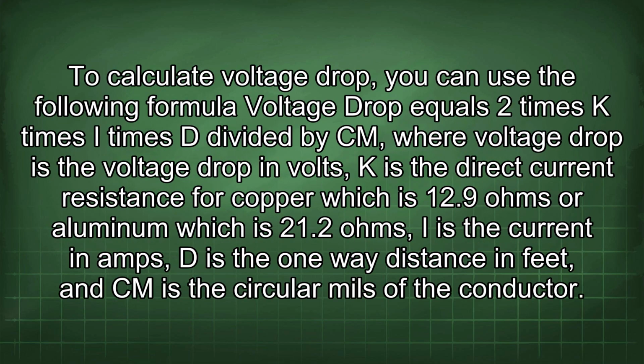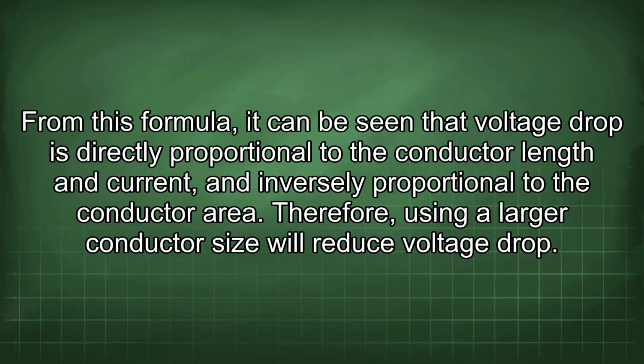To calculate voltage drop, you can use the following formula: voltage drop equals 2 times K times I times D divided by Cm, where voltage drop is the voltage drop in volts, K is the direct current resistance for copper, which is 12.9 ohms, or aluminum, which is 21.2 ohms, I is the current in amps, D is the one-way distance in feet, and Cm is the circular mils of the conductor. From this formula, it can be seen that voltage drop is directly proportional to the conductor length and current, and inversely proportional to the conductor area. Therefore, using a larger conductor size will reduce voltage drop.